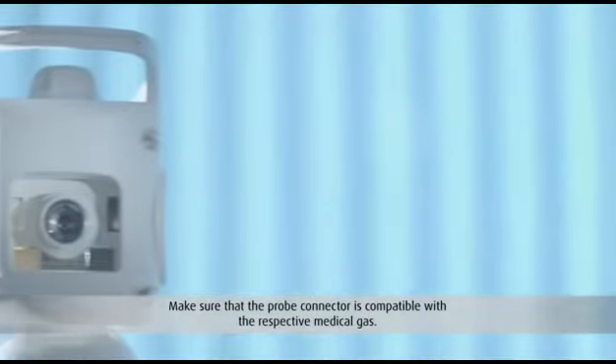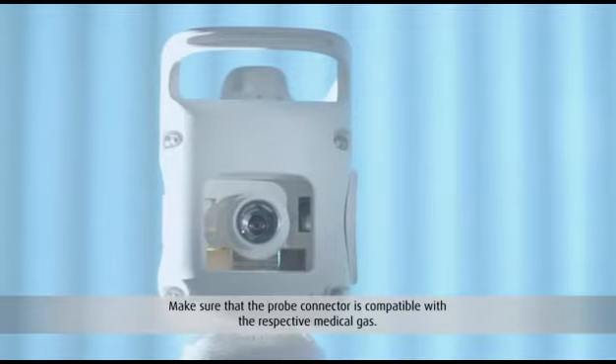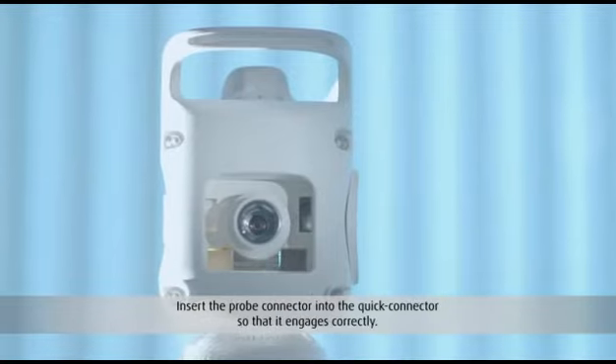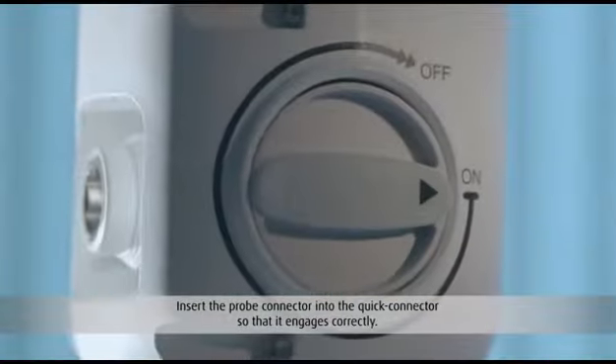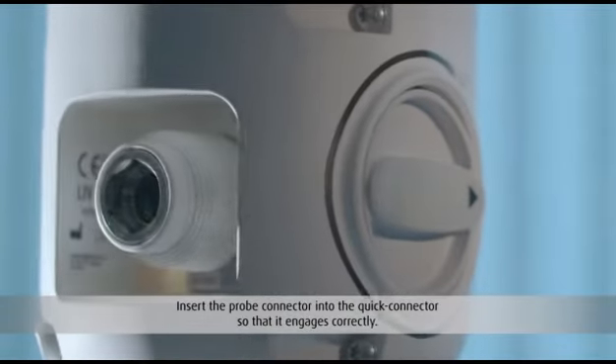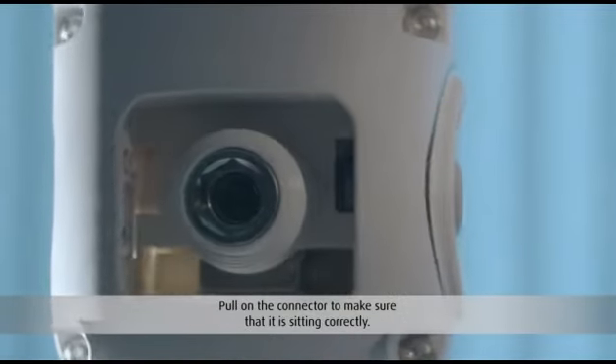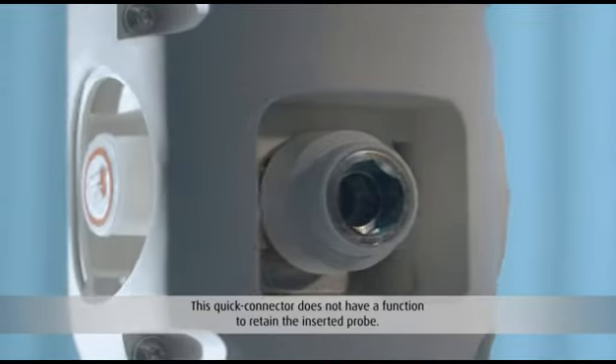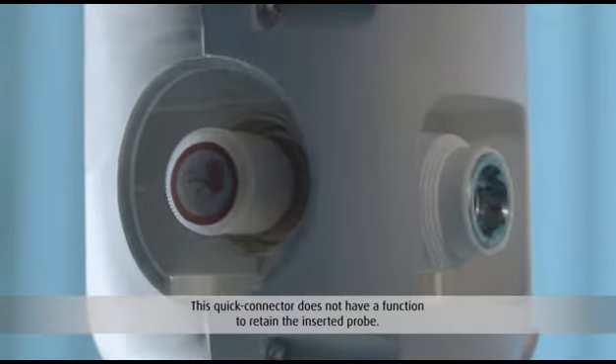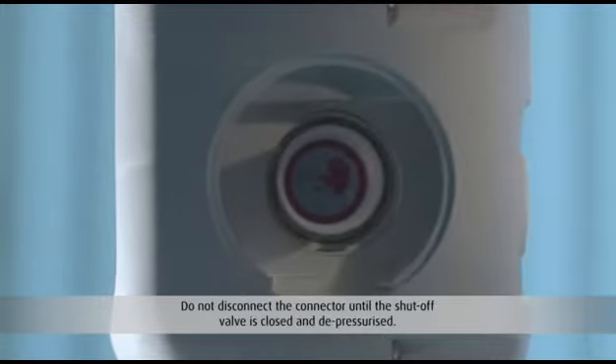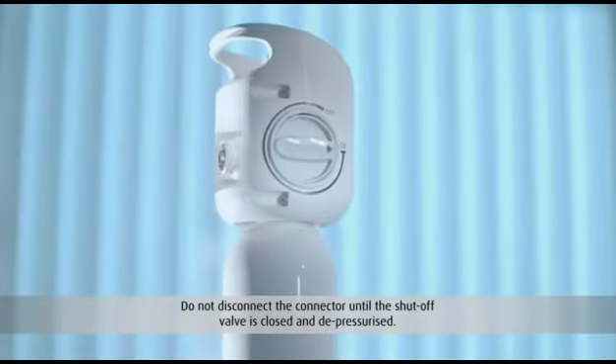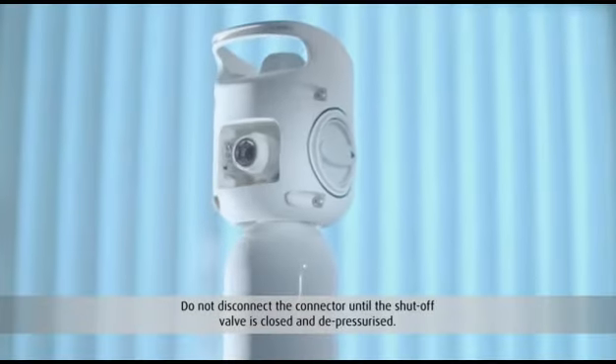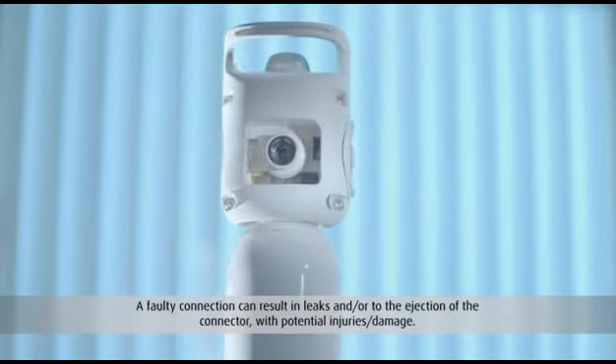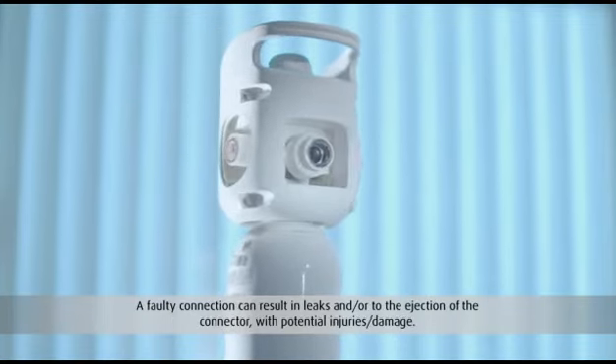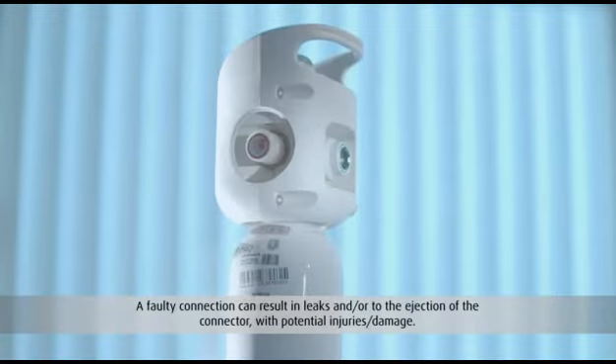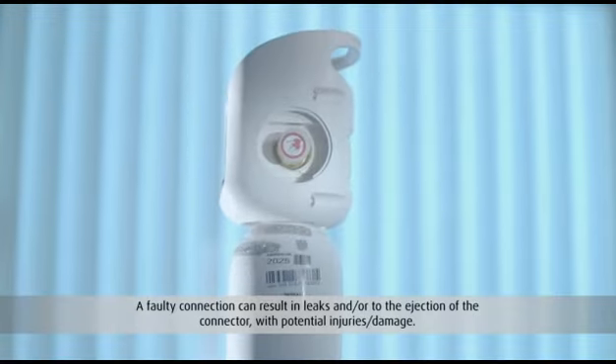make sure that the probe connector is compatible with the respective medical gas. Insert the probe connector into the quick connector so that it engages correctly. Pull on the connector to make sure that it is sitting correctly. This quick connector does not have a function to retain the inserted probe. Do not disconnect the connector until the shutoff valve is closed and depressurized. A faulty connection can result in leaks and/or to the ejection of the connector, with potential injuries or damage.